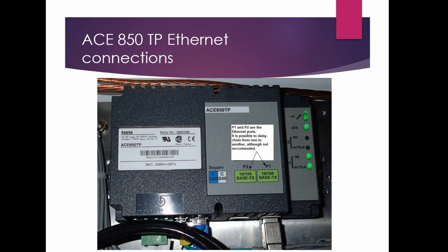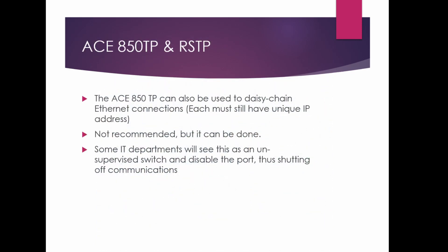On your ACE850TP module, the blue connector goes to the CPAM — marked F — and you connect your incoming Ethernet to either P1 or P2. It's possible to daisy-chain from one module to the next, bringing in on P1 and going out on P2 to the next compartment, but we don't recommend doing that. If you do daisy-chain, each CPAM still must have a unique IP address. Some IT departments will see this as an unsupervised switch and disable the port, shutting off your communications.